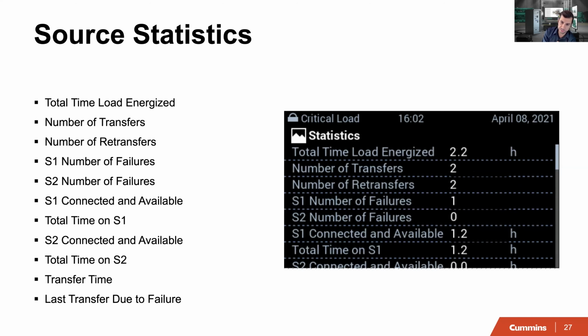There is source statistics, so this would help you if you want to investigate a problem with the utility, for example. If we keep losing utility and you have the number of failures in the utility, you want to investigate and see, well, what's the problem with the utility? It captures the number of transfers, the number of failures, the total time that the transfer switch has been connected to one source or another.